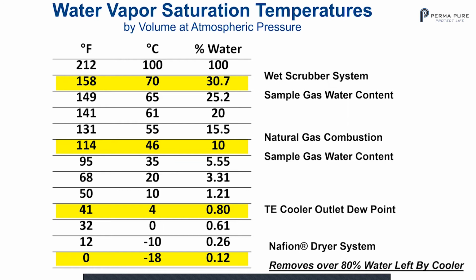This is one of the reasons why you have so much less problems with your analyzer and much less analyzer maintenance, because we don't have that water vapor in the sample gas that's going to recombine with the components that we're looking to measure to create acids.